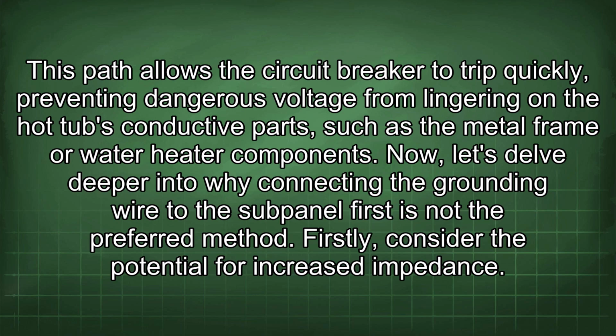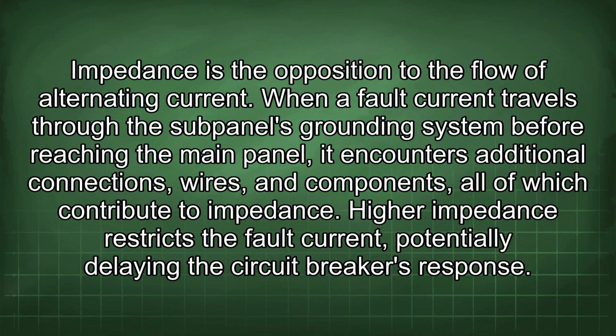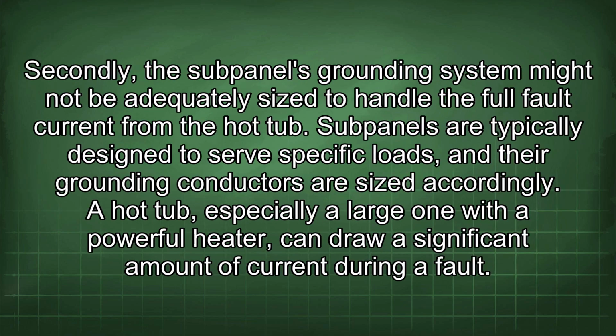Now, let's delve deeper into why connecting the grounding wire to the subpanel first is not the preferred method. Firstly, consider the potential for increased impedance. Impedance is the opposition to the flow of alternating current. When a fault current travels through the subpanel's grounding system before reaching the main panel, it encounters additional connections, wires, and components, all of which contribute to impedance. Higher impedance restricts the fault current, potentially delaying the circuit breaker's response. Secondly, the subpanel's grounding system might not be adequately sized to handle the full fault current from the hot tub. Subpanels are typically designed to serve specific loads, and their grounding conductors are sized accordingly.